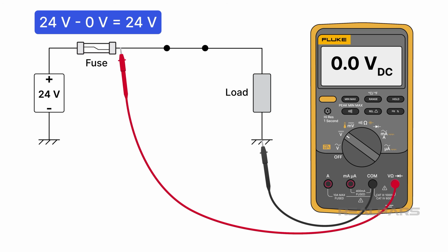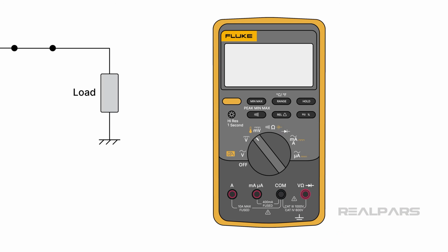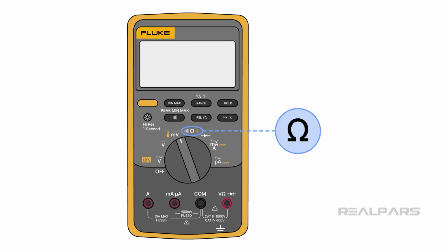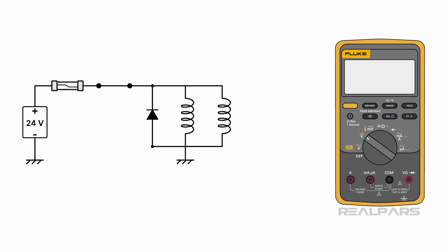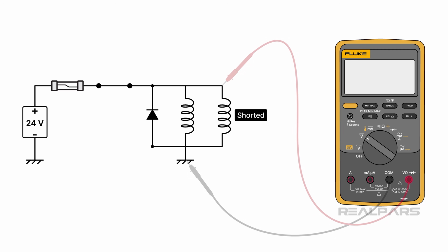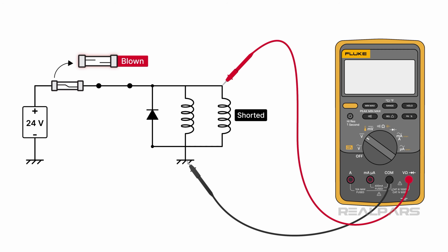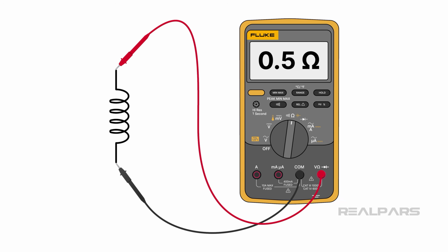Just to be clear, voltage measurement isn't a one-size-fits-all approach. For example, sometimes you have no alternative but to use your ohm meter because a voltmeter measurement is not possible. For example, if one solenoid is shorted in a two-solenoid parallel configuration, no voltage measurements will help to identify the defective solenoid. Why not? Because the fuse will be blown, opening the circuit. The solenoids must be tested individually using an ohm meter.